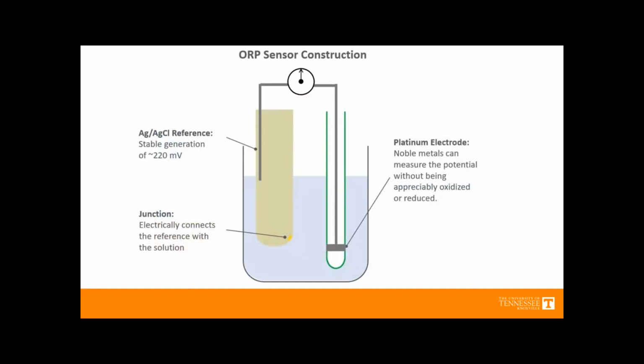What is tricky is this part right here. In our reference electrode, in order to have an electrical circuit and to measure that potential, I need to complete an electrical circuit, right? Current has to flow. If I just have this in a solid tube, I wouldn't get any readings, because, this is my voltmeter up at the top, I need to move charge around in a circle. So I need some way for charged particles or ions to move. And you've got that little rubbery thing at the end of our reference electrode. That's going to let ions move into and out of this electrode.